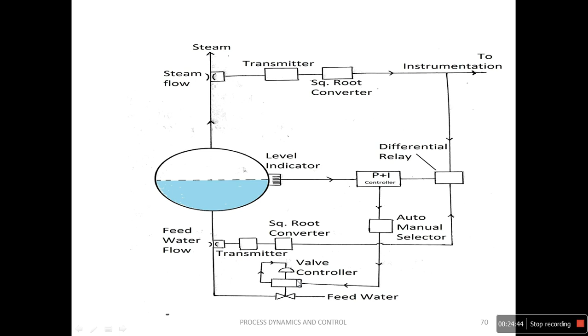If the level is not maintained as required, all the boiler tubes are not covered and may be left without water, and they may get overheated and damaged. In the other way, if there is an increase in the level, it may interfere with the process of separating moisture from steam within the drum, thus reducing the boiler efficiency and carrying moisture into the process or turbine.